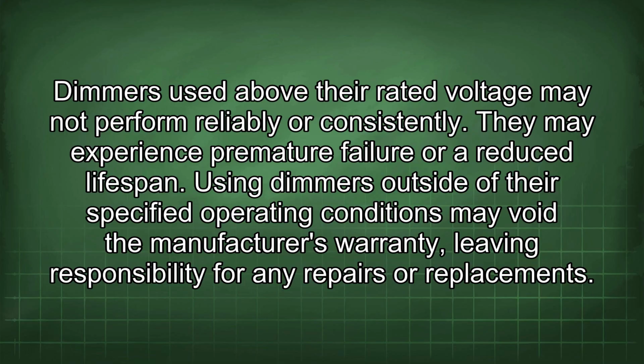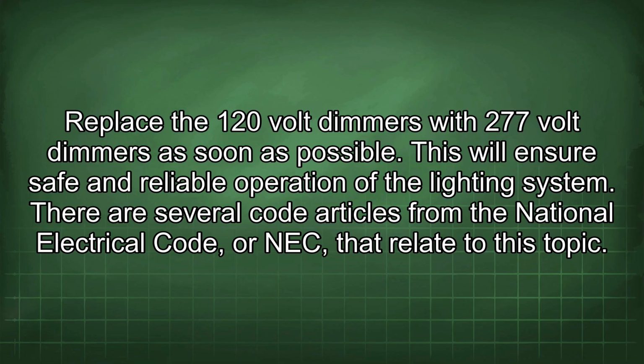Using dimmers outside of their specified operating conditions may void the manufacturer's warranty, leaving you responsible for any repairs or replacements. Replace the 120-volt dimmers with 277-volt dimmers as soon as possible. This will ensure safe and reliable operation of the lighting system. There are several code articles from the National Electrical Code, or NEC, that relate to this topic.